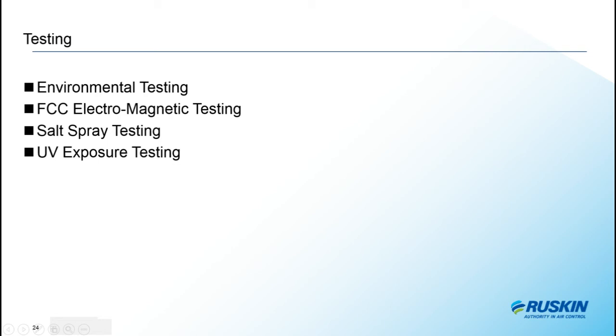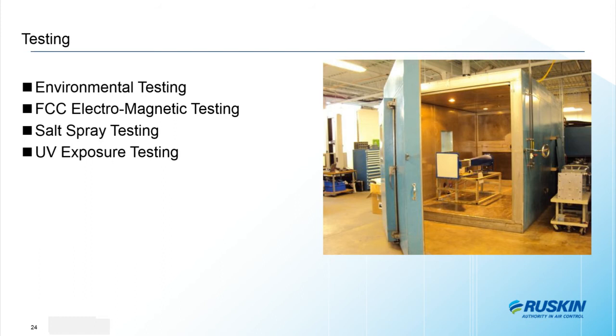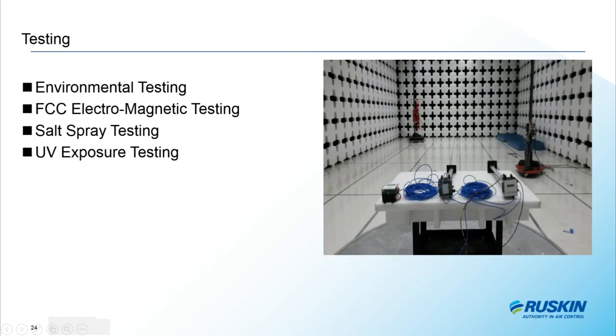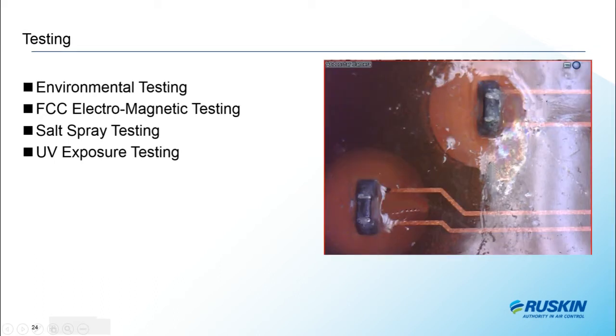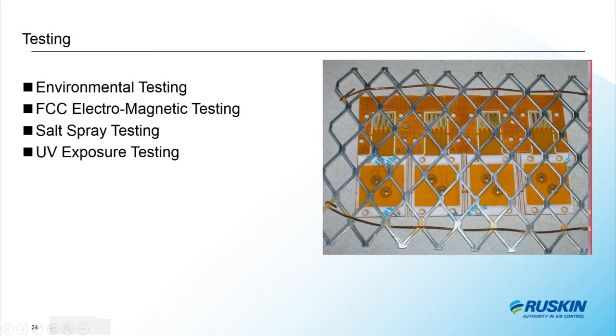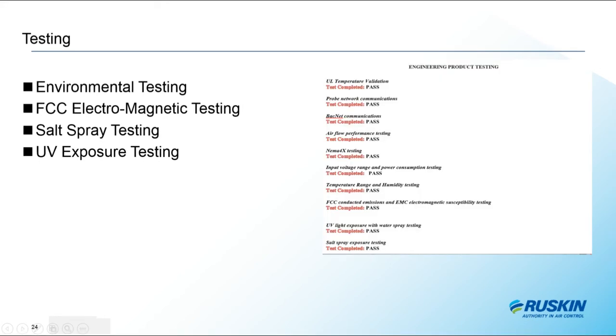The TDP05K is an extensively tested product. Environmental testing, with a really big freezer that transitions into a hot box, was used to validate the full range of operating temperatures. Electromagnetic testing proved this product is not emanating radio waves and is not affected in the presence of radio waves. Salt spray testing established that this is the most durable sensor on the market today. And UV exposure testing. The materials used have been carefully selected for this application, and much more. Each test passed with flying colors, or modifications and enhancements were made to the product to make sure the product we have today is the most reliable product.